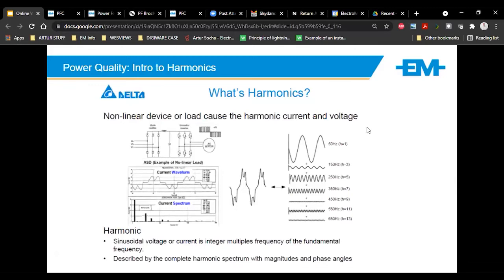Okay, so I'm just going to do a brief example here. This is the internals of a variable speed drive, the very basic internals. I've got power coming in and I've got power going to my motor. But as we know, a variable speed drive has what we call IGBTs. It's got gates, and those gates fire at specific frequencies. That causes, let's call it, a clipping on the output power, but that effect is seen on the input power, so it's seen on your internal grid. I'll run through a quick example of what this would look like.